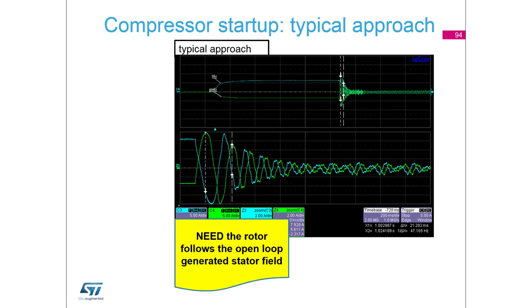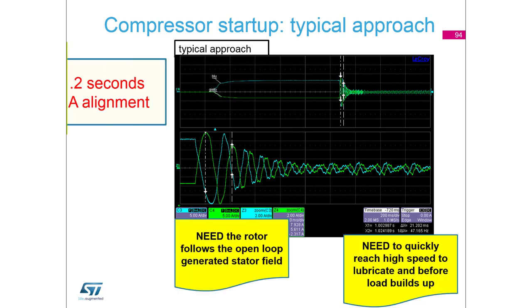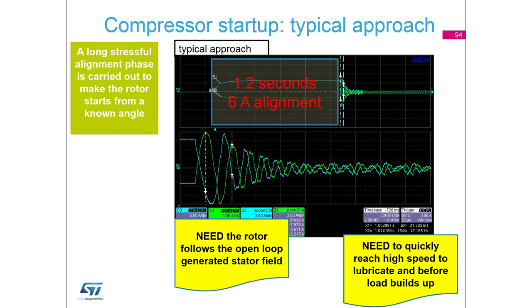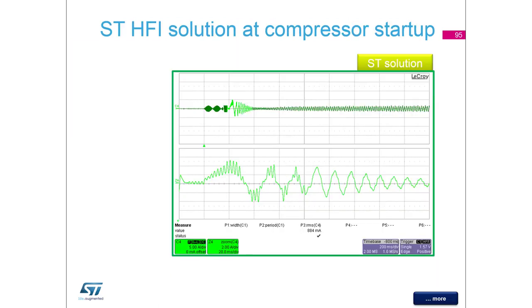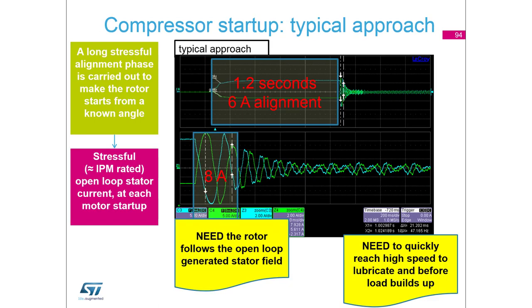Looking inside: the first part is alignment - more than one second with six amperes, which is quite a high current. Then we have eight amperes for a very short open-loop startup. Then it switches to closed loop, and it could be the same with HFI.